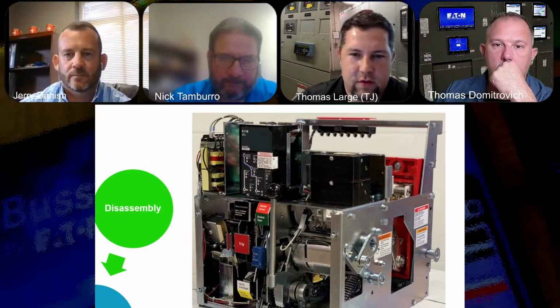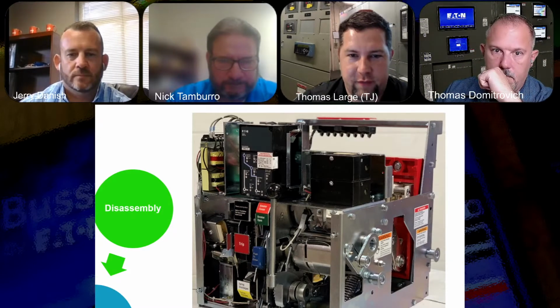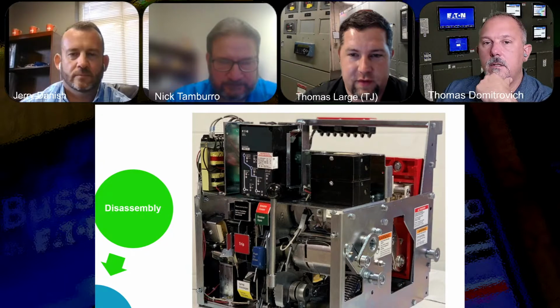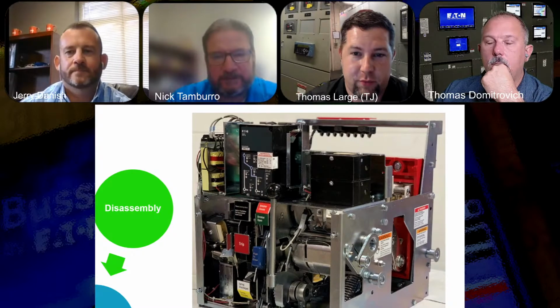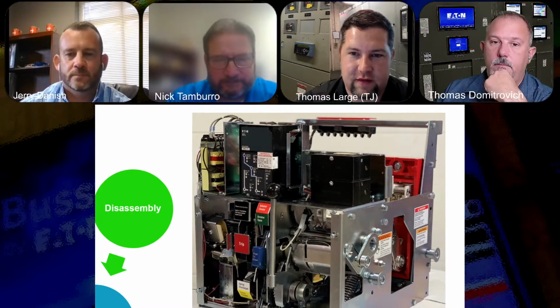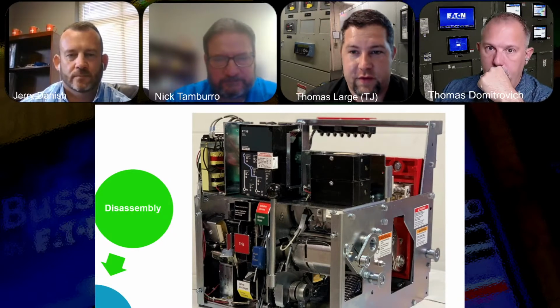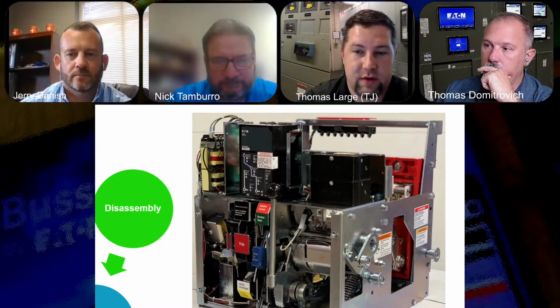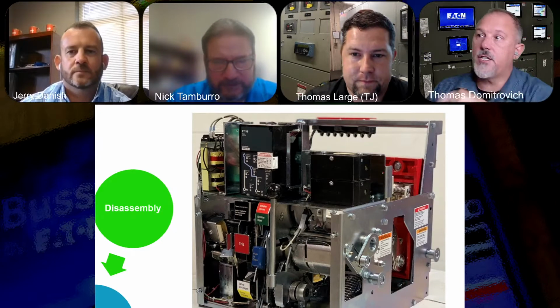Let's say you're on this specific breaker, you go from Amptector to DS. The curve changes with the newer trip unit, but also with these retrofits and upfits, you get the increased modern protection capabilities such as ARMS, right? So you get that personal protection piece that's not accessible for your vintage equipment, but we're giving it today's standards of protection for equipment and employees. Yeah. So that's the point.